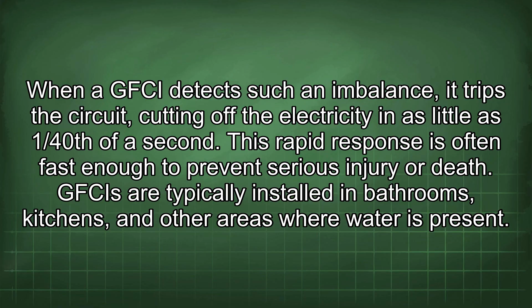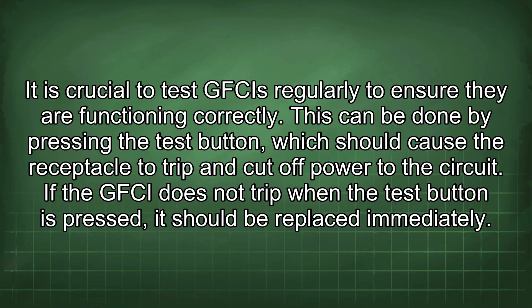This rapid response is often fast enough to prevent serious injury or death. GFCIs are typically installed in bathrooms, kitchens, and other areas where water is present. They can be identified by the presence of test and reset buttons on the face of the receptacle. While GFCIs are highly effective, they are not foolproof. They can fail due to age, damage, or improper installation. It is crucial to test GFCIs regularly to ensure they are functioning correctly. This can be done by pressing the test button, which should cause the receptacle to trip and cut off power to the circuit.